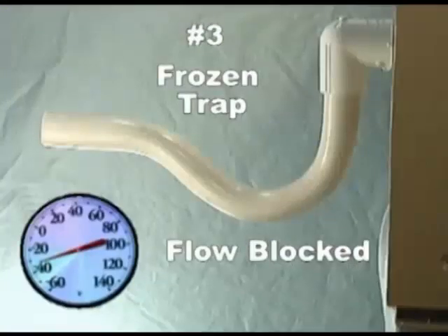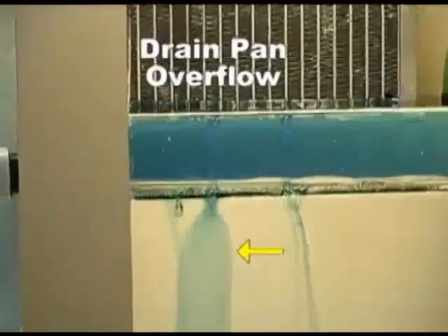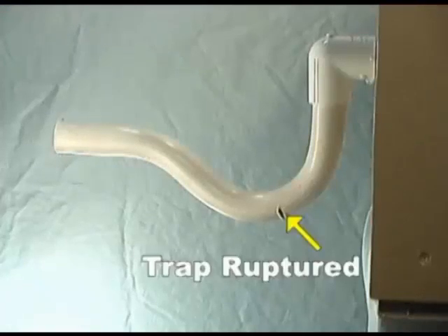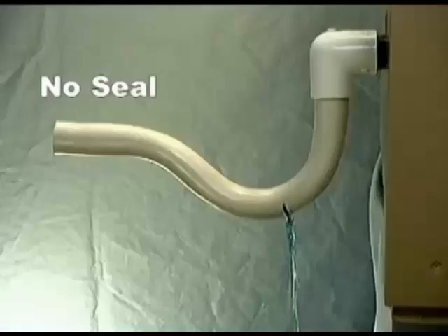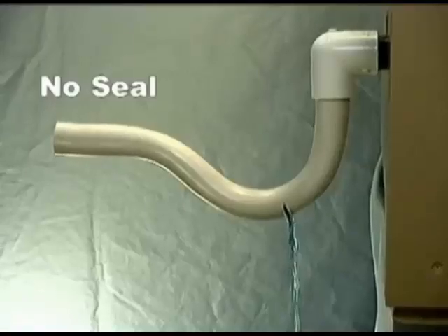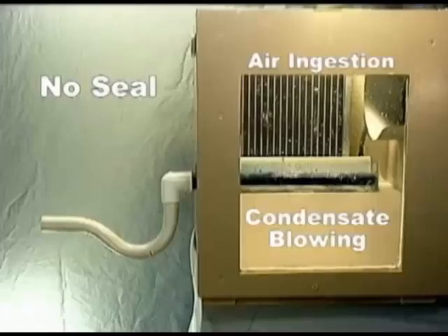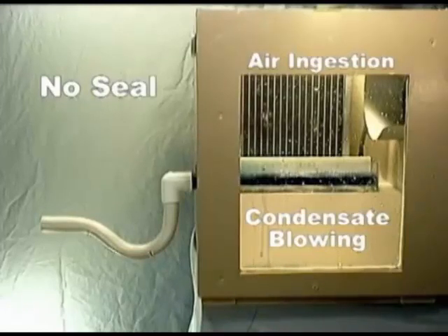Condensate traps exposed to freezing temperatures will block the flow of condensate, causing drain pan overflow. When condensate freezes, the trap is frequently ruptured, as depicted here. Because it cannot retain condensate, there is no seal and it acts like an empty or missing trap. Observe that water leaks from the trap and allows air ingestion and condensate blowing during the cooling operation.